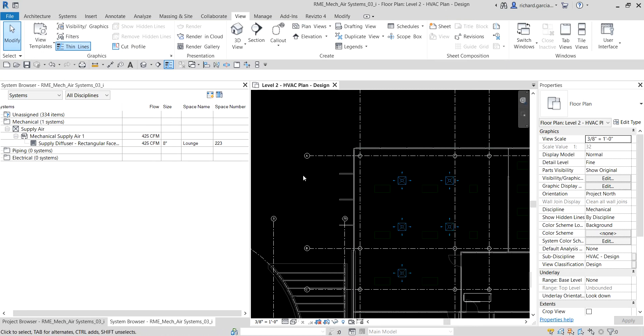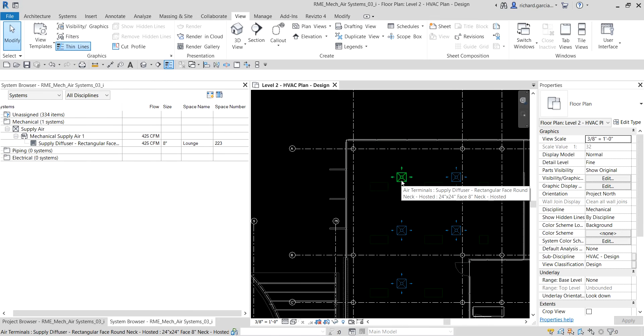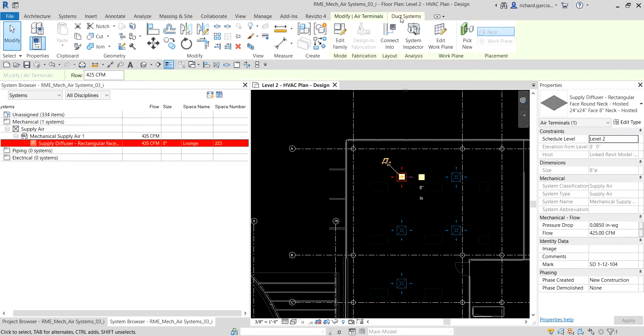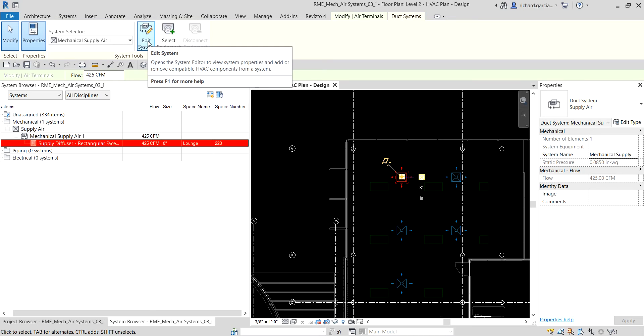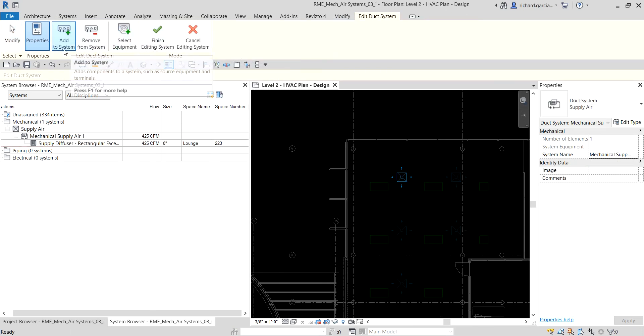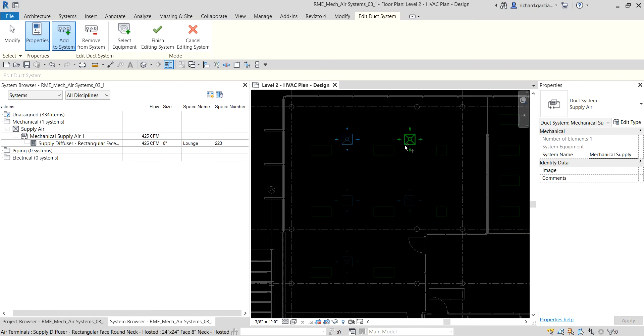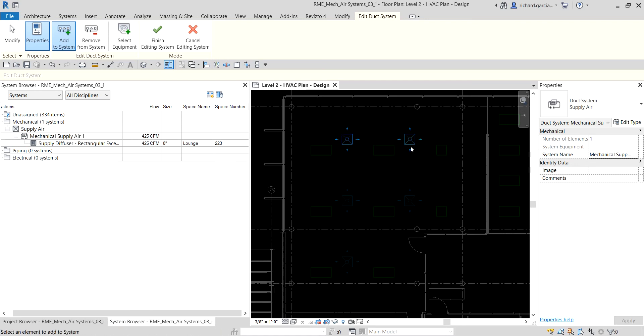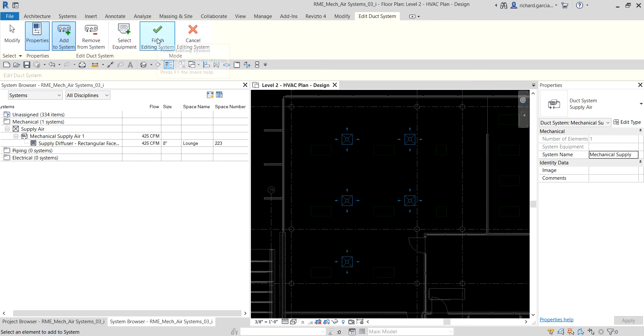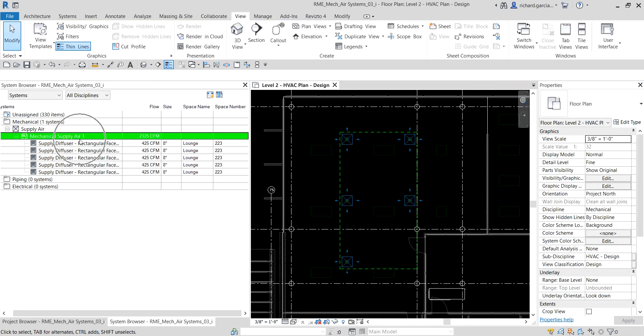To add the other four air terminals to the system, click an air terminal that is already part of the system, then go to 'Duct Systems' and click 'Edit System'. By default, 'Add to System' is already activated. Simply select the additional air terminals you want to add. Once done, click 'Finish Editing System' and the system browser will update accordingly.